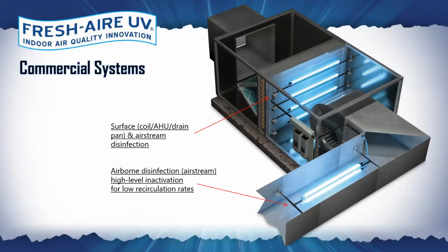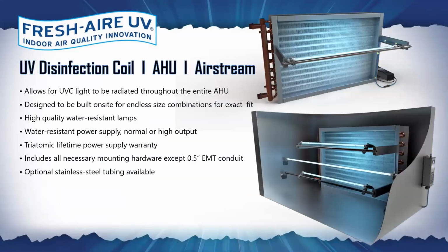We want to dilute the number of pathogens in the air, and UV in the air handling unit will achieve that. So our UV system for coil mount is really simple. We try to keep it simple. A lot of our competitors use very, very elaborate metalwork, unistrut, racking. The freight cost alone could be more expensive than the lamps and power supplies. We don't want to go down that road. We try to make things so easy that we're even using magnets in the example you see there. So our UV system uses 12-inch brackets. They get mounted to the frame of the coil or the wall of the air handler. And we also use magnet mounts to hold or position the lamps as well. A very, very easy, refined, simple installation.